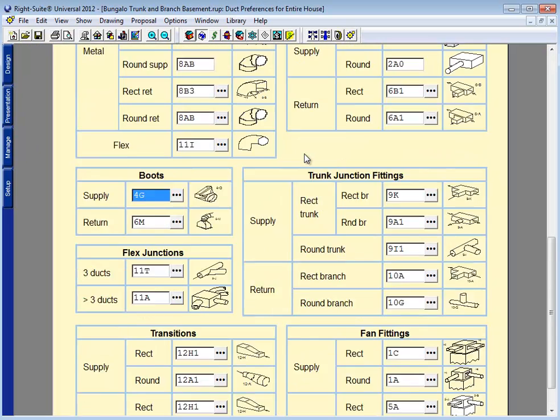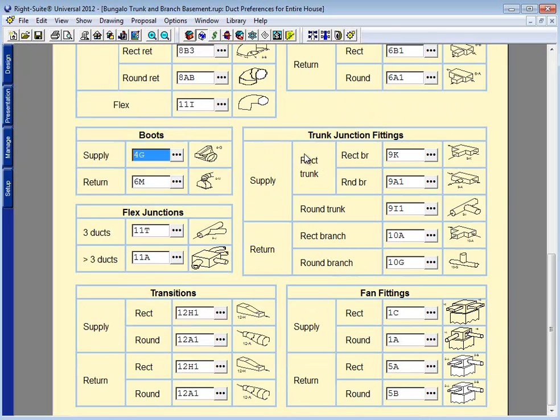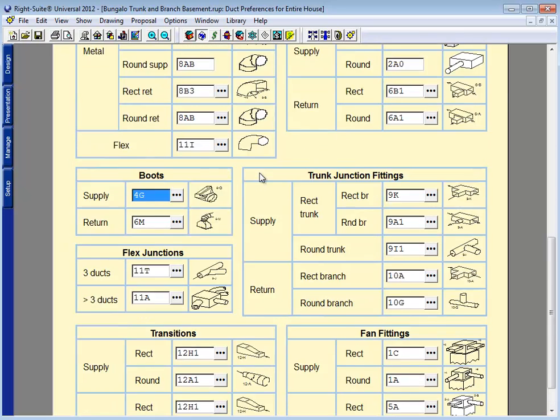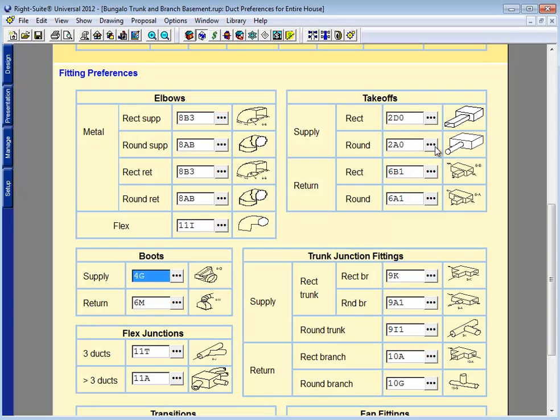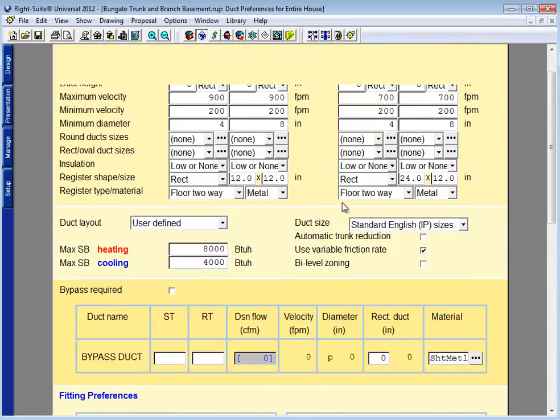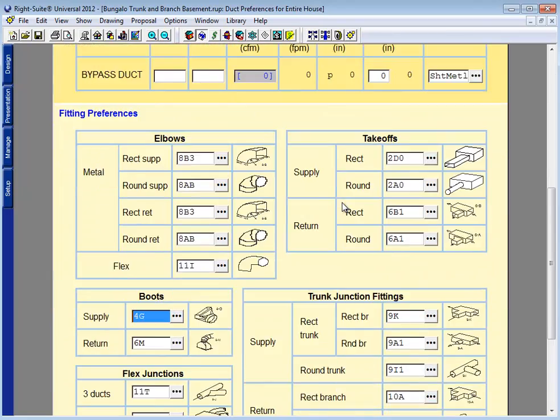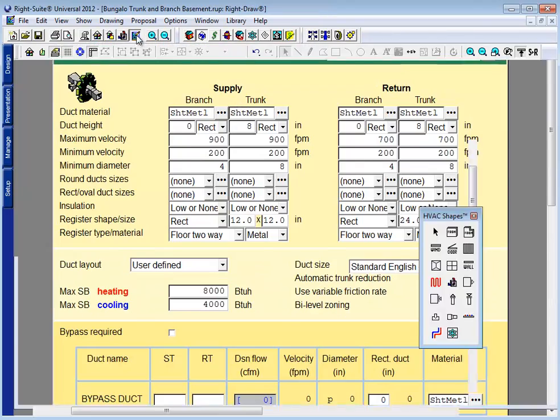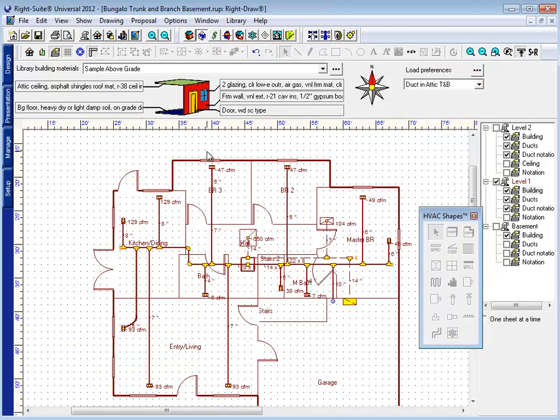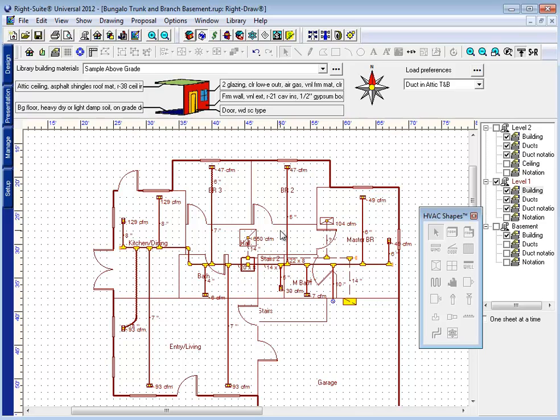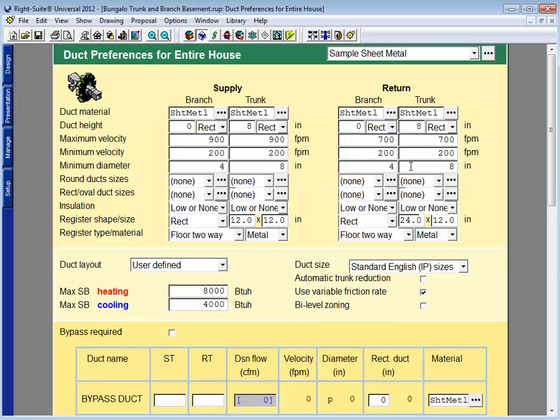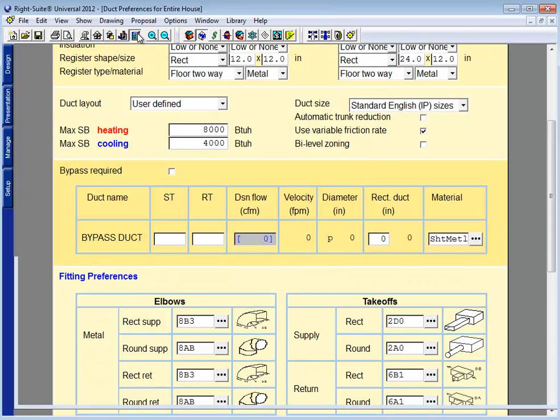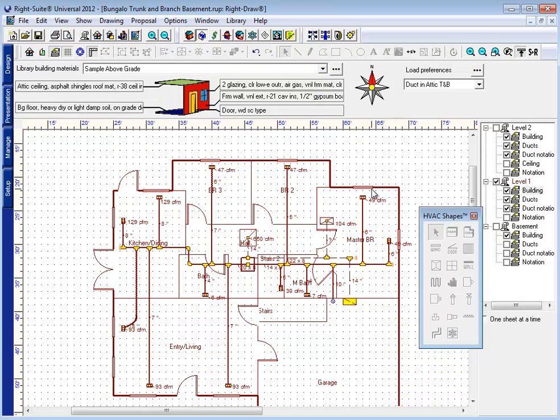Next, I should revisit my duct preferences page. I might be using different boots or different fittings, top takeoffs instead of side takeoffs in a basement. Making any adjustments to this duct preferences page will automatically adjust any duct or fitting or part of the duct system that hasn't been manually changed. So as long as I haven't made manual adjustments, making a change here will affect the entire design.